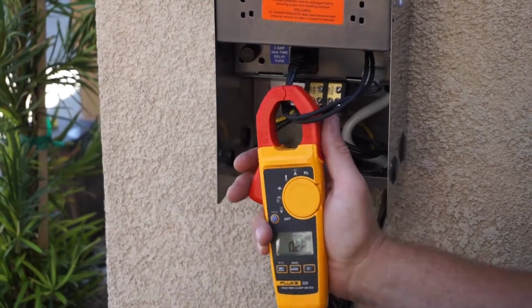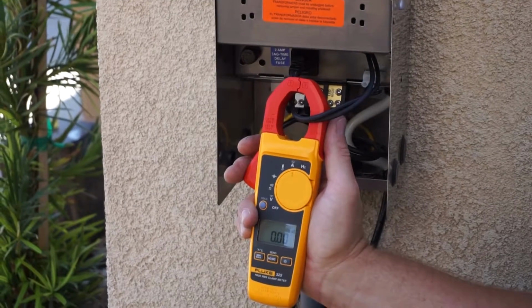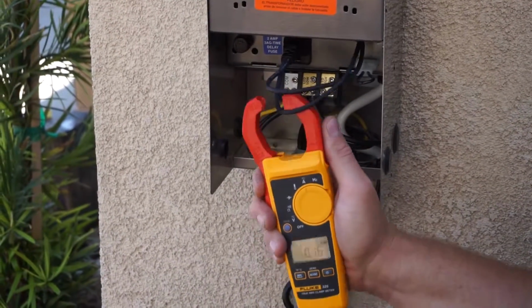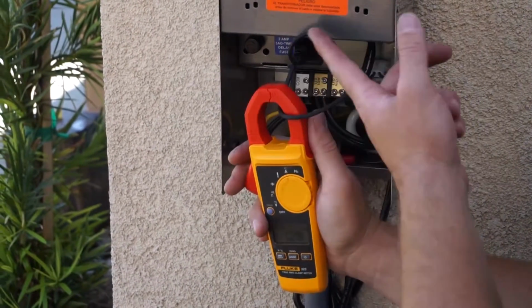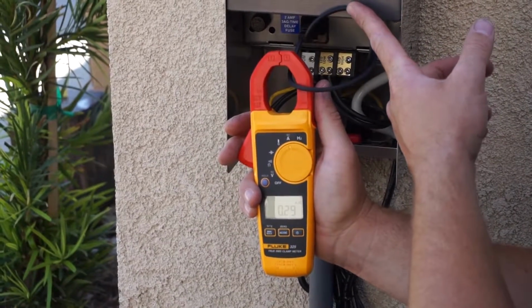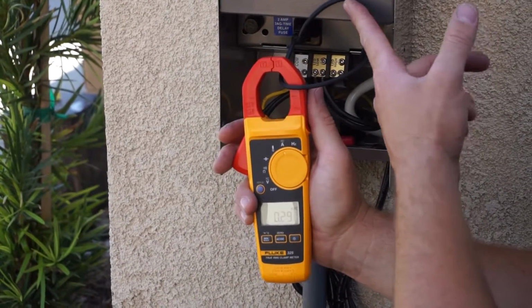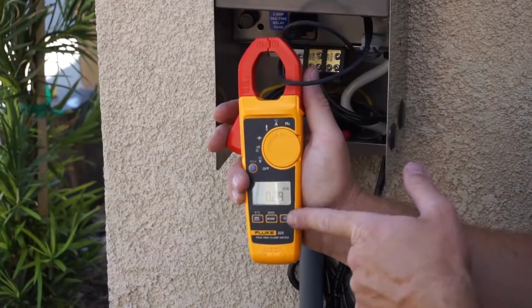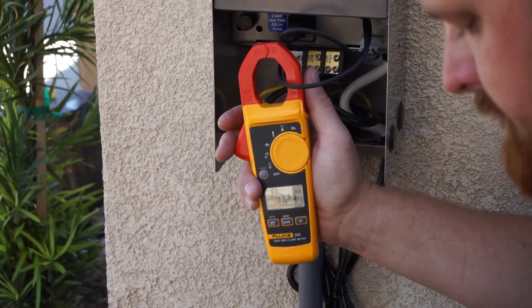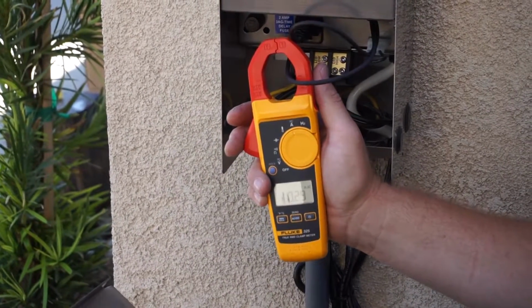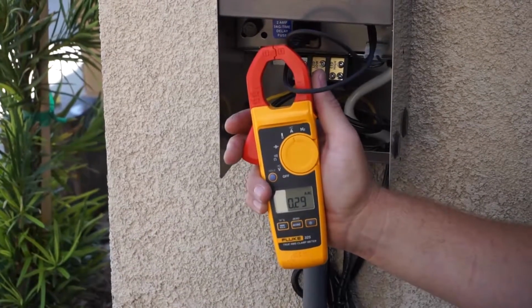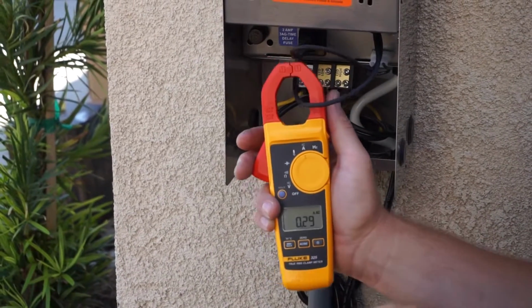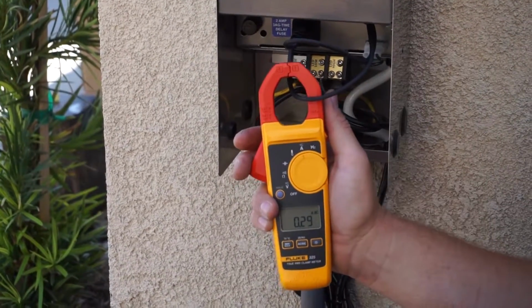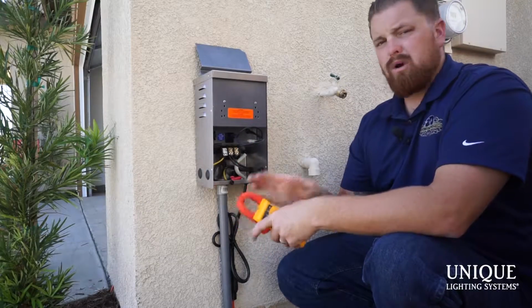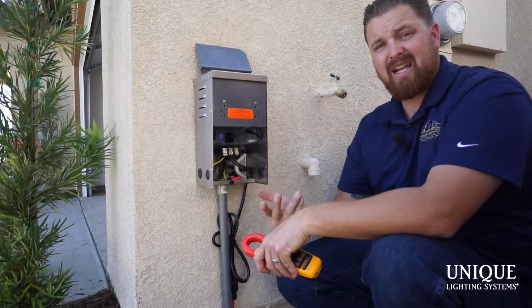So if I were to check both, you're going to see that it's going to eventually zero out and say nothing at all. But if I check just one or the other, so now I've just connected to one, I'm at 0.29 amps. And then if I check the other one, it'd do the same thing. So 0.29 amps compared to my 1.66 amps, I'm well within range, so I'm way under power on this transformer, which is perfect. So that's primary amps. The second of the critical three is secondary amps.